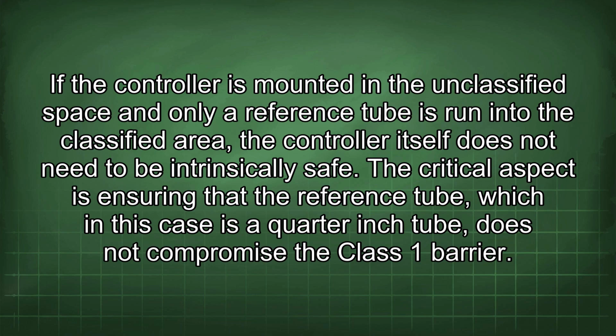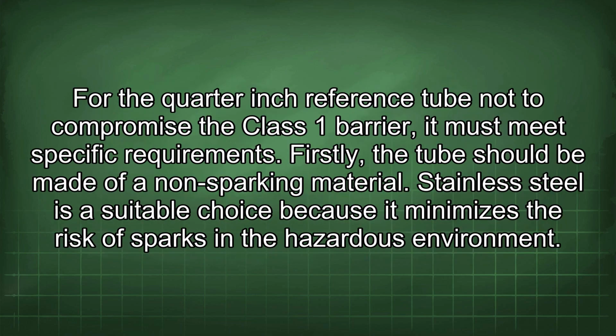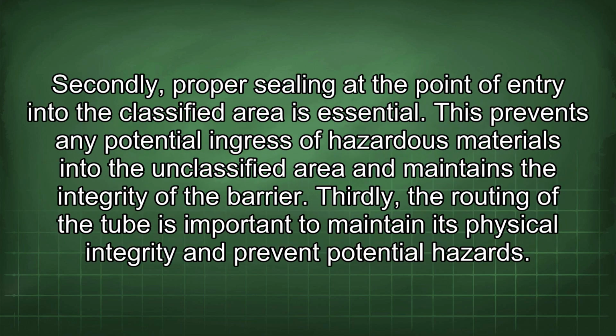The critical aspect is ensuring that the reference tube, which in this case is a 1/4-inch tube, does not compromise the Class 1 barrier. For the 1/4-inch reference tube not to compromise the Class 1 barrier, it must meet specific requirements. Firstly, the tube should be made of a non-sparking material. Stainless steel is a suitable choice because it minimizes the risk of sparks in a hazardous environment. Secondly, proper sealing at the point of entry into the classified area is essential. This prevents any potential ingress of hazardous materials into the unclassified area and maintains the integrity of the barrier.